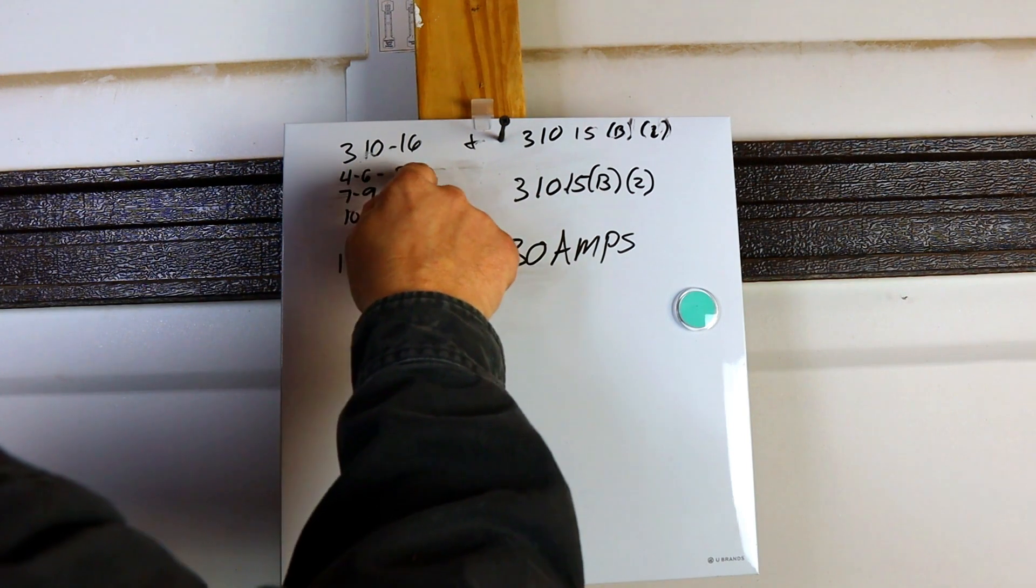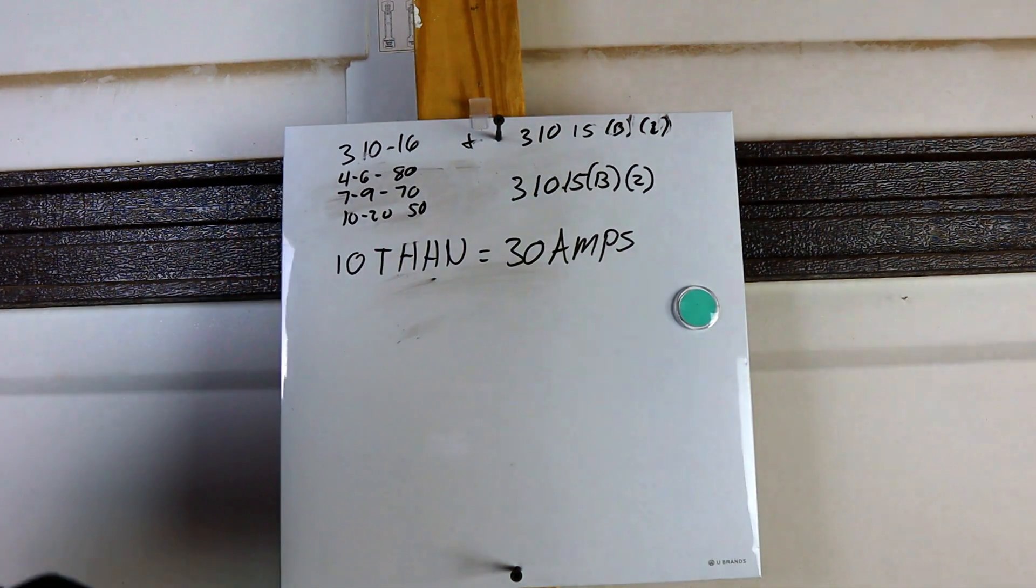This 310-16 is for the amps and the wire size. This 310-15(B)(2) tells you how many current carrying conductors you have to start de-rating for. So between 4 and 6, it has to be 80%. 7 and 9, 70%, 10 through 20, which is 50%. Now, what does all that mean?